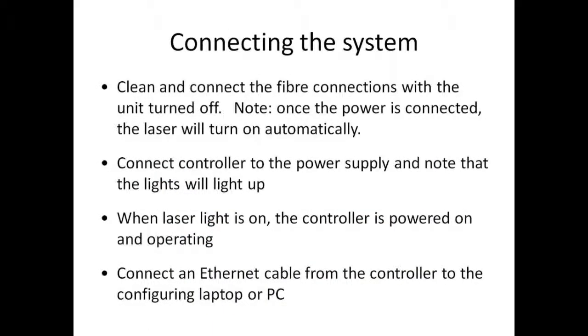Connecting the system up is simple. Firstly, clean and connect the fibre optic connections with the unit turned off. You need to note that once the power is connected, the laser will turn on automatically. After cleaning the fibre optic connectors, then you connect the controller to the power supply, and you'll note that the lights on the front light up. When the laser light is on, the controller is powered on and operating. Then you connect your Ethernet cable from the controller to your configuring laptop or PC.